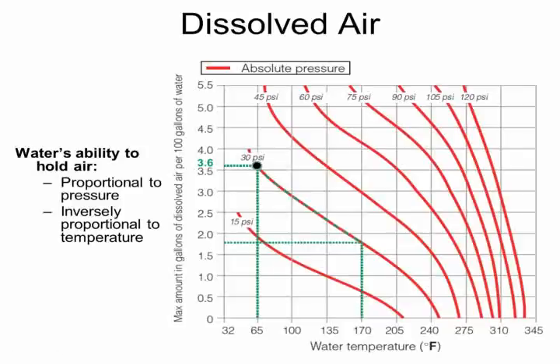Now let's simulate that we fire the boiler on for the first time and show this effect of air coming out of solution. As water heats up, it wants to expand, but you have put an expansion tank on your system, so the pressure isn't going to change. So as you heat the water up from 65, let's say we're going to heat it up to 170, not an untypical temperature, we're just going to ride right down this curve to here, at which point the amount of air that's in solution now is 1.8 gallons. We started at 3.6. We lost half of our air. What happened to the air? It came out of the solution. It's running around in the form of air bubbles and eventually air pockets.